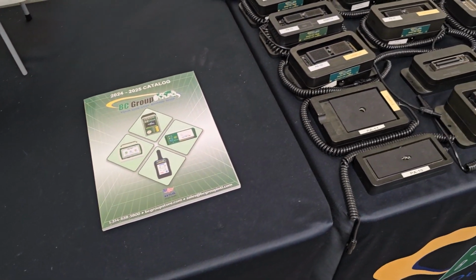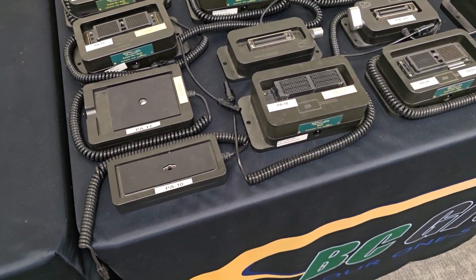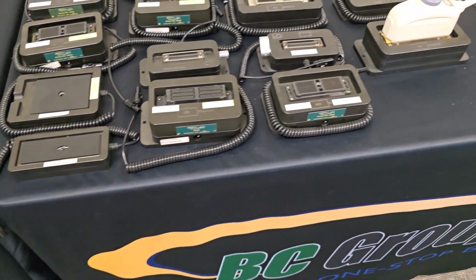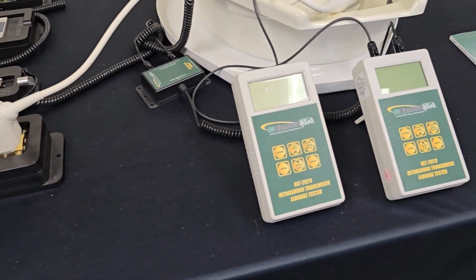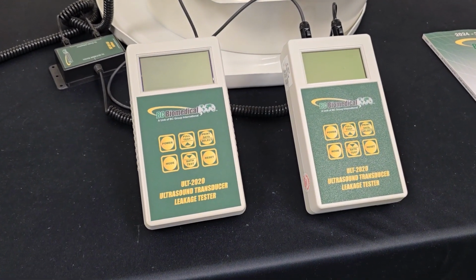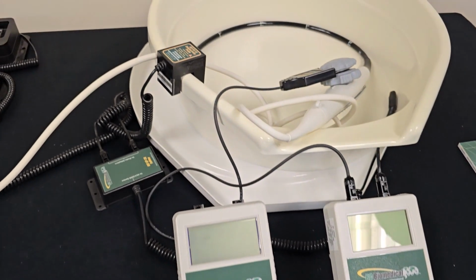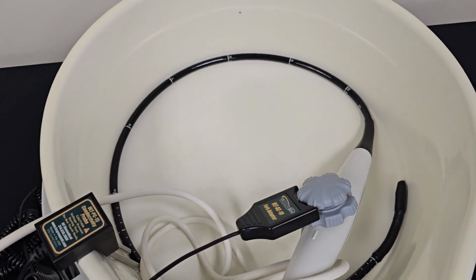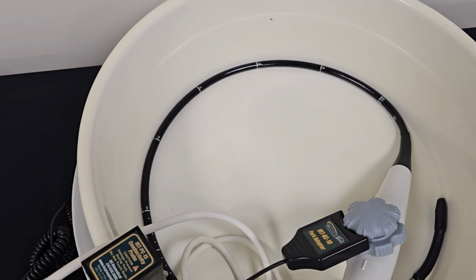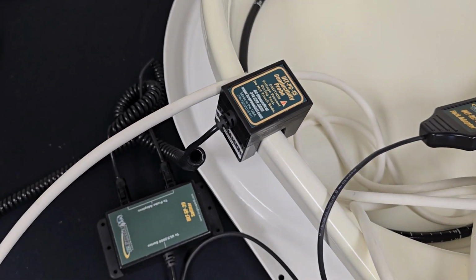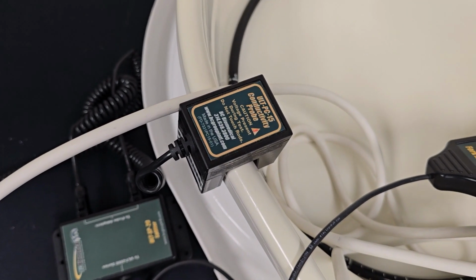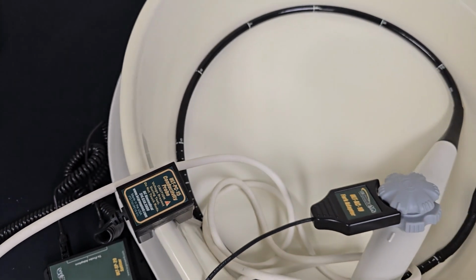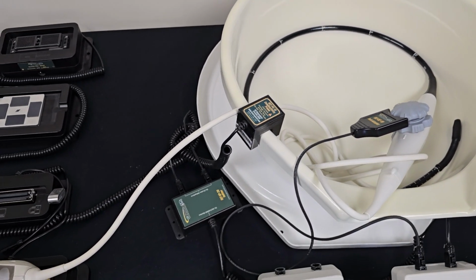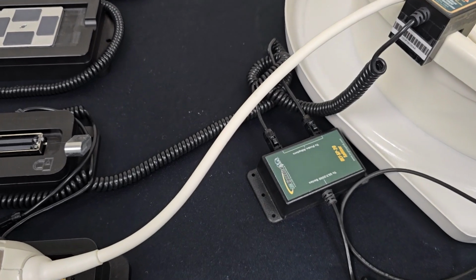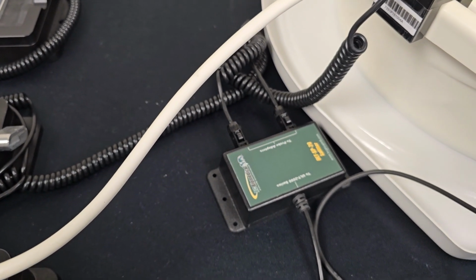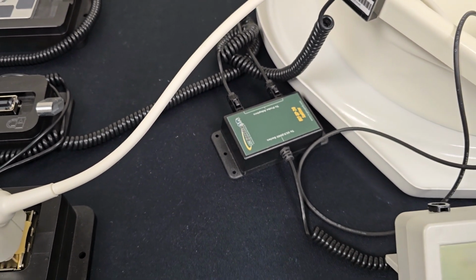Oh, look at all these. Now these, what are these for? So these are for doing TEE ultrasound transducer testing, and not just for TEEs. That's just the most common type. But the ultrasound transducers, they used to be tested every year, just to make sure that they're safe and not leaking. But around 2015 or so, there was a mandate that came out that said they need to be tested in between each use. And so that really grew the need for this particular product line.